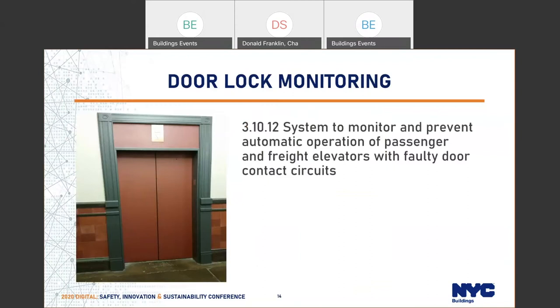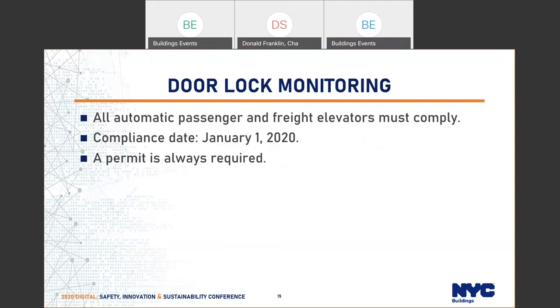For door lock monitoring, to improve safety, BC 2014 Appendix K Chapter K3 retroactively required all passenger and freight elevators to have a system to monitor and prevent automatic operation with faulty door contact circuits. This system should not work in Phase 2 firefighter's operation. The compliance date was January 1st, 2020. A permit is always required to do this work, even if you are doing just a software update. The compliance date has already passed and there are still some devices rushing to comply.